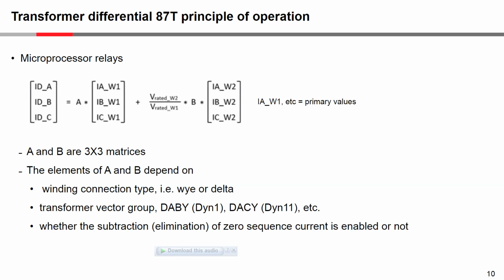So looking a bit more into the matrix equation, okay, we have these 2 matrices, the A and the B matrix, A on winding 1 and B on winding 2. They are 3x3 matrices, and the elements of these matrices depend on the winding connection type. In other words, is it a Y winding or a delta winding? It depends on the transformer vector group. Okay, so remember the vector group is actually what is really giving you the phase difference from one winding to the next. And also the elements depend on whether the subtraction or elimination of 0 sequence current is enabled or not.